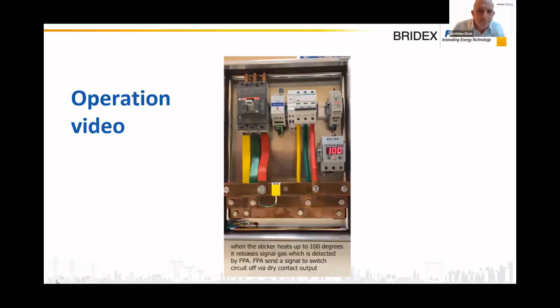So let's have a close look at the overall degradation of contact and how the fire really starts. Usually the degradation occurs within months and with different temperature cycling, always reaching higher temperature. And then once the contacts are really degraded, in a few minutes, it can lead to fire.